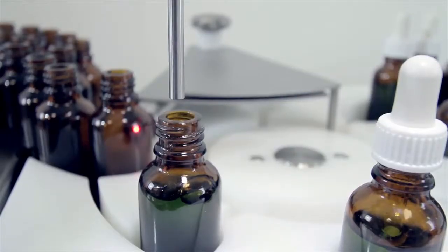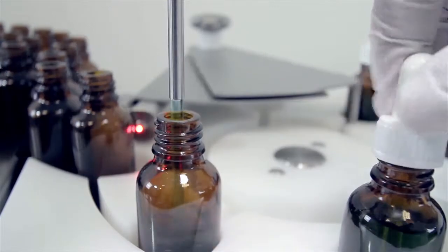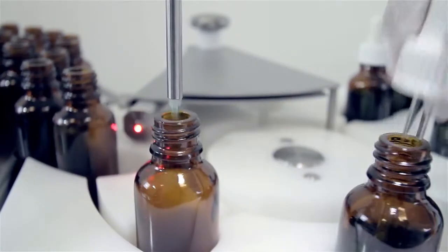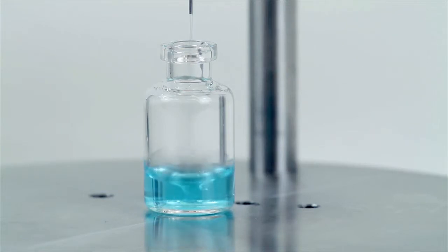Foaming, splashing or dripping between each fill is always unacceptable. The adjustable fill speed and acceleration of the PF6 filler prevents splashing and foaming while dripping is stopped using a back suction function.